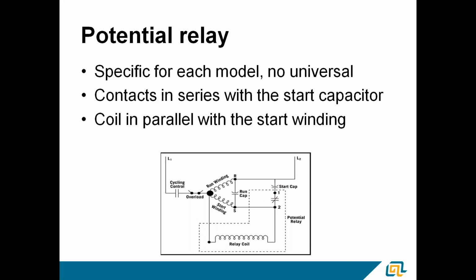So it's always kind of been a little bit of a mystery. People call me and talk to me about them: what is it doing? And I explain it, and you can see it's really a pretty straightforward system. They operate on what they call pickup and dropout voltage, and that's where you really see how specific these relays are, because they'll have a very narrow band where they pick up or drop out. Pickup would be open the relay, dropout is close the relay again as the compressor comes to a stop.